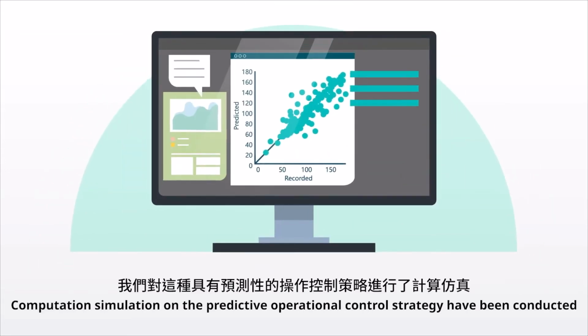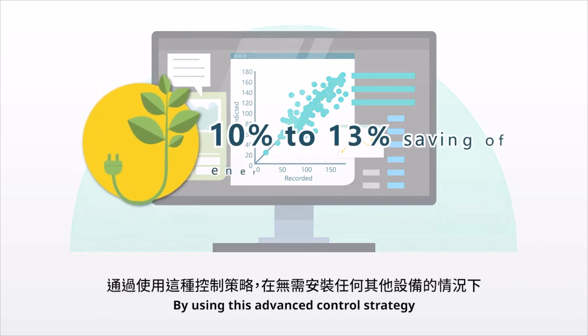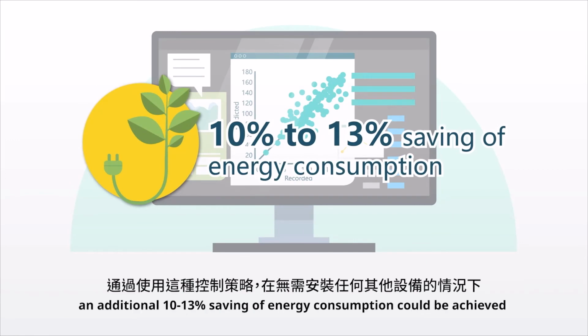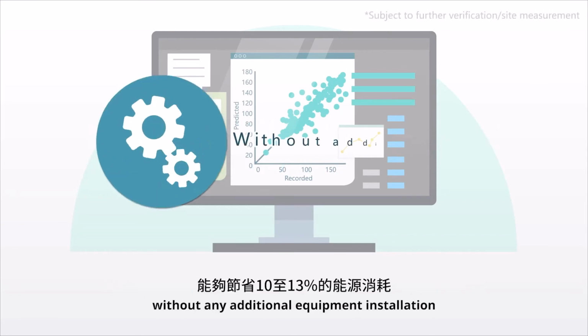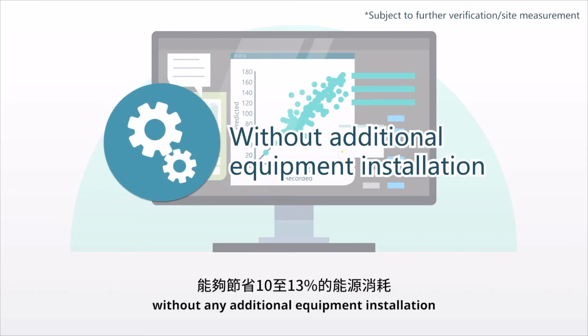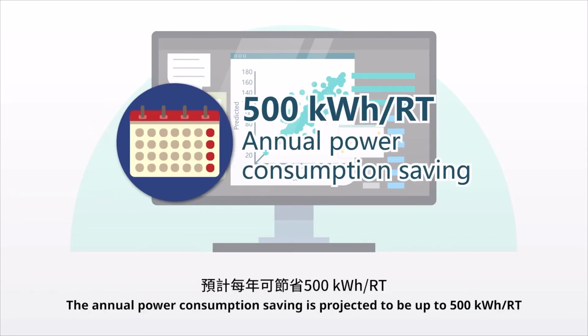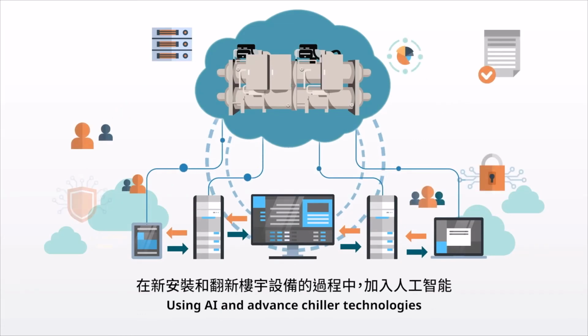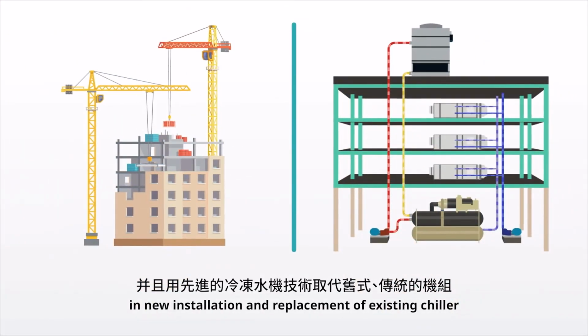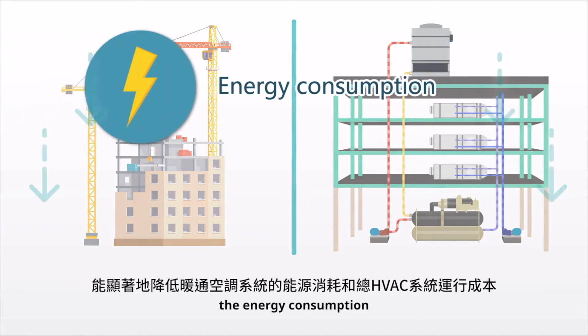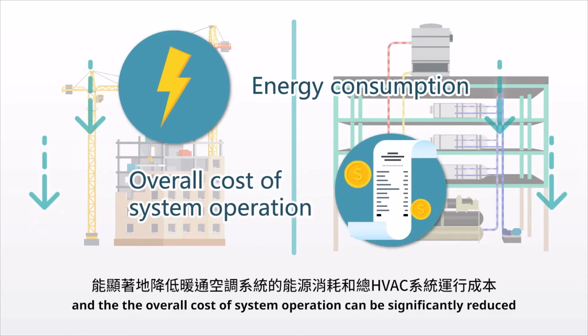Computational simulation on the predictive operational control strategy has been conducted. By using this advanced control strategy, an additional 10% to 13% saving of energy consumption could be achieved without any additional equipment installation. The annual power consumption saving is projected to be up to 500 kilowatt-hour per refrigeration ton. Using AI and advanced chiller technologies in new installation and replacement of existing chillers, the energy consumption and the overall cost of system operation can be significantly reduced.